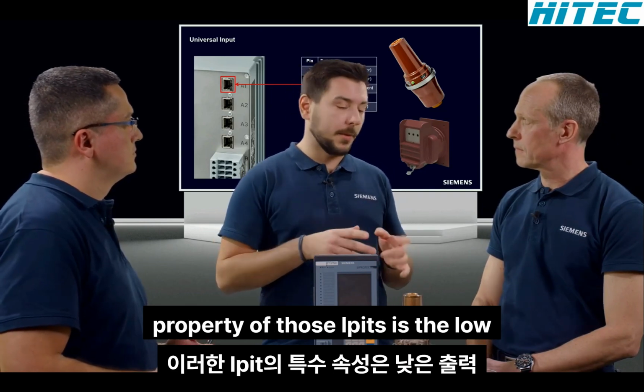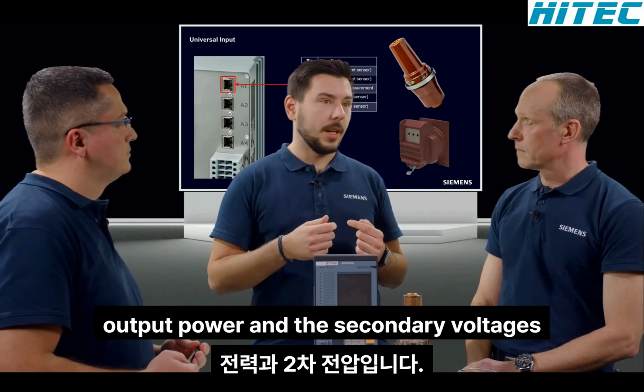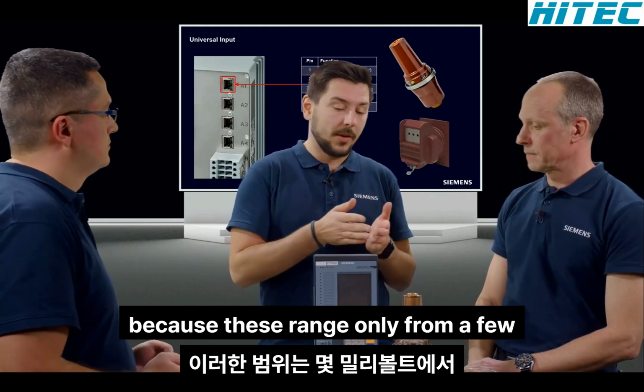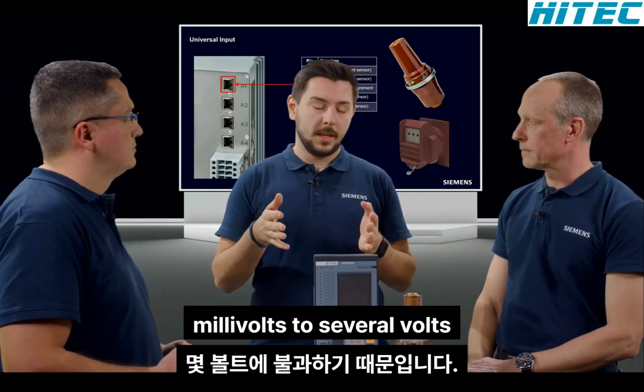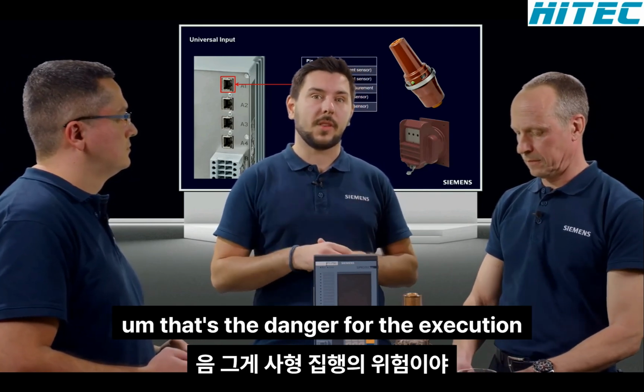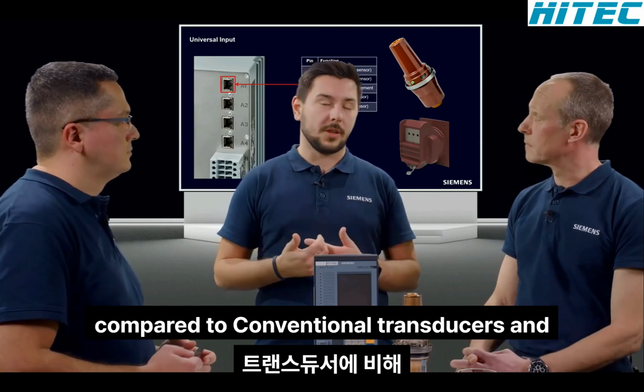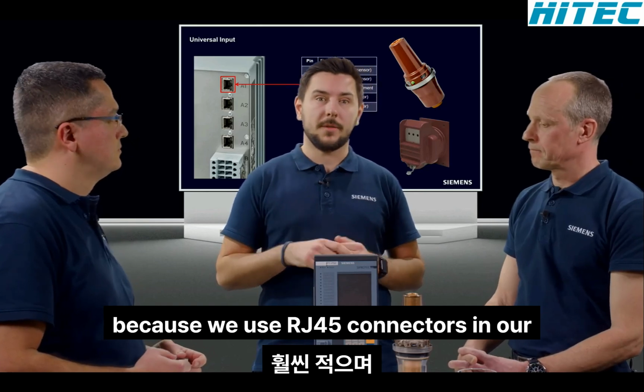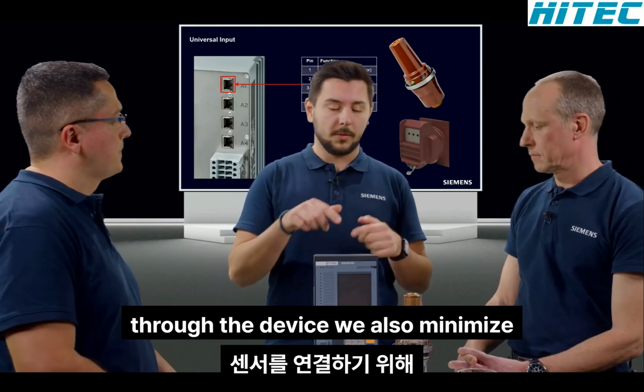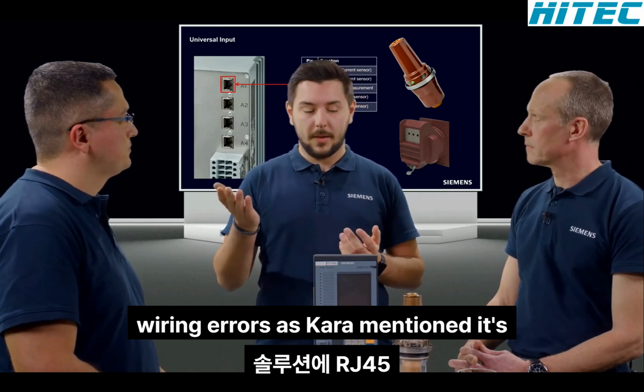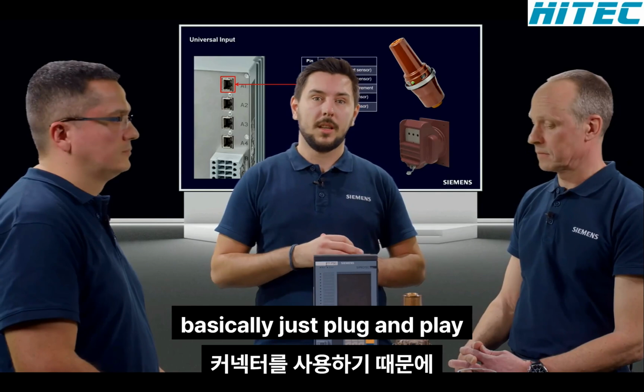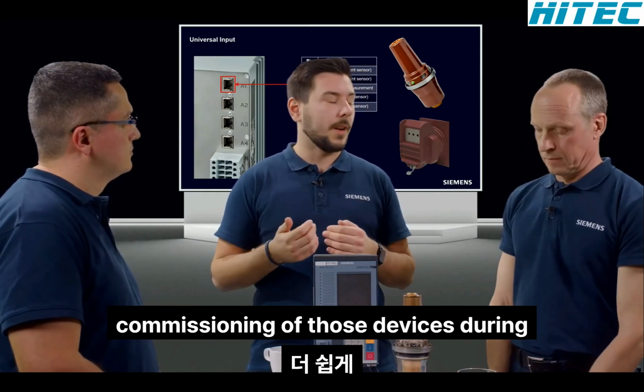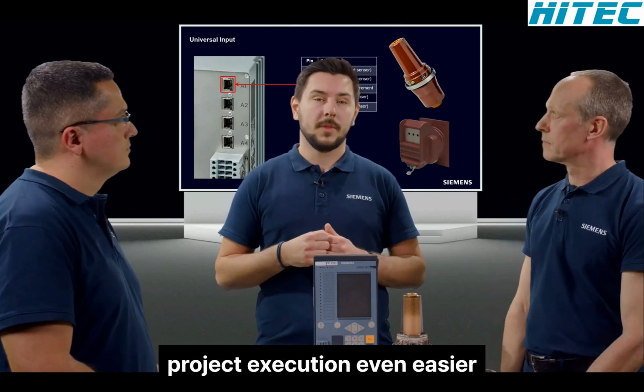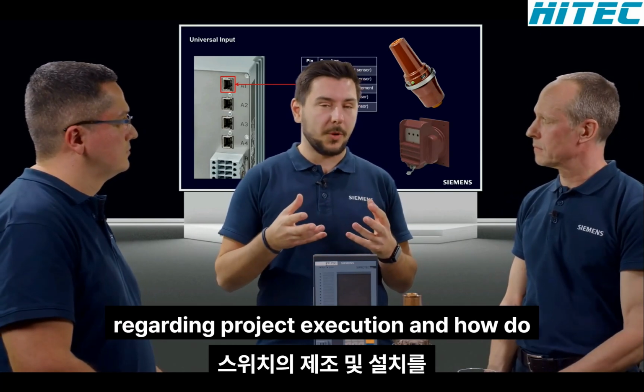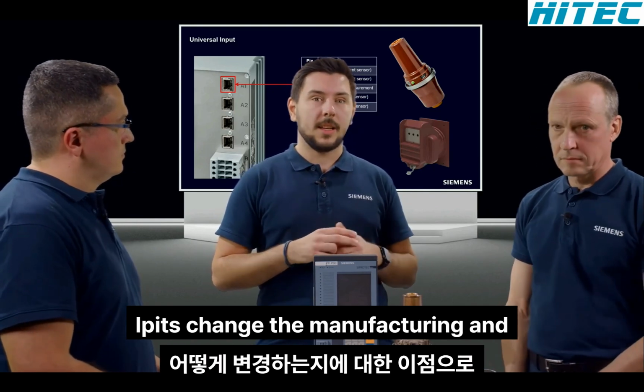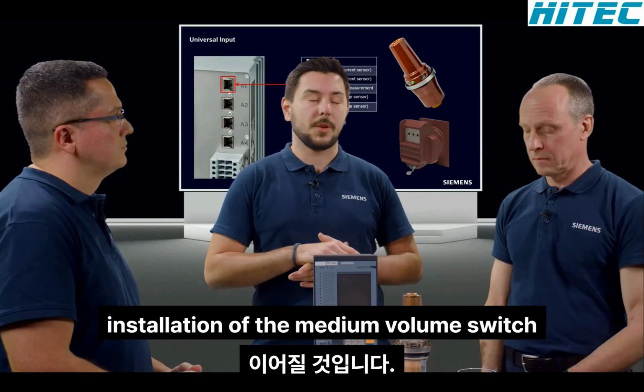And as you mentioned, the special property of those LPITs is the low output power and the secondary voltages, because these range only from a few millivolts to several volts. Thus, the danger for the execution personnel is significantly lower compared to conventional transducers. And because we use RJ45 connectors in our solution for connecting the sensors to the device, we also minimize wiring errors. As Kara mentioned, it's basically just plug and play, which is making installing and commissioning of those devices during project execution even easier. This would also lead us to benefits regarding project execution. But how do LPITs change the manufacturing and installation of the medium voltage switchgears?